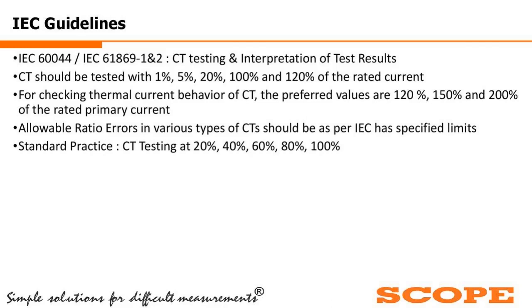IEC 61869-1 and -2 specifies allowable ratio errors and accuracy limits. For standard practice, CTs can also be tested at 20%, 40%, 60%, 80%, and 100% of rated current. These are the standard test practices.